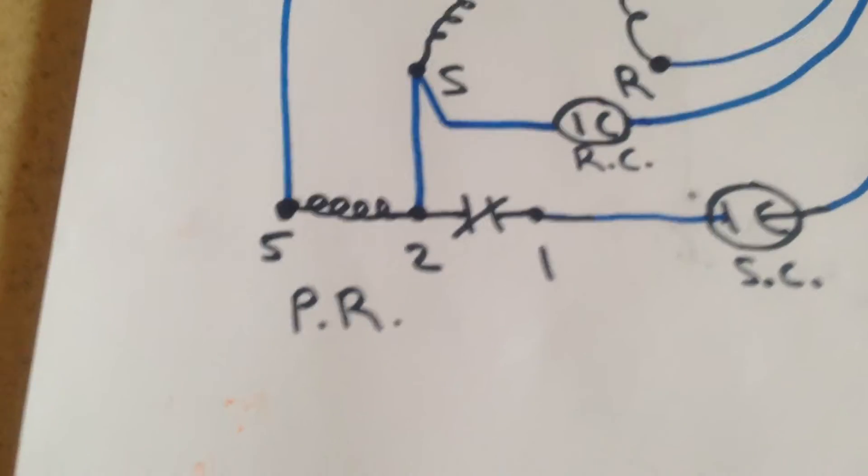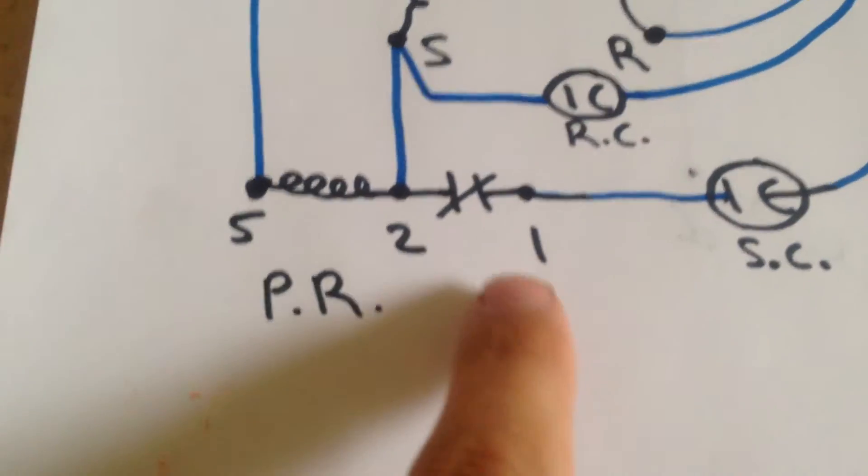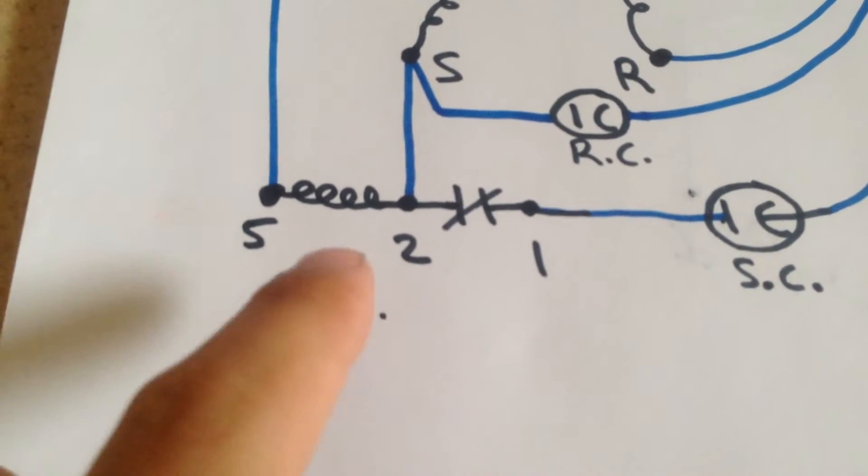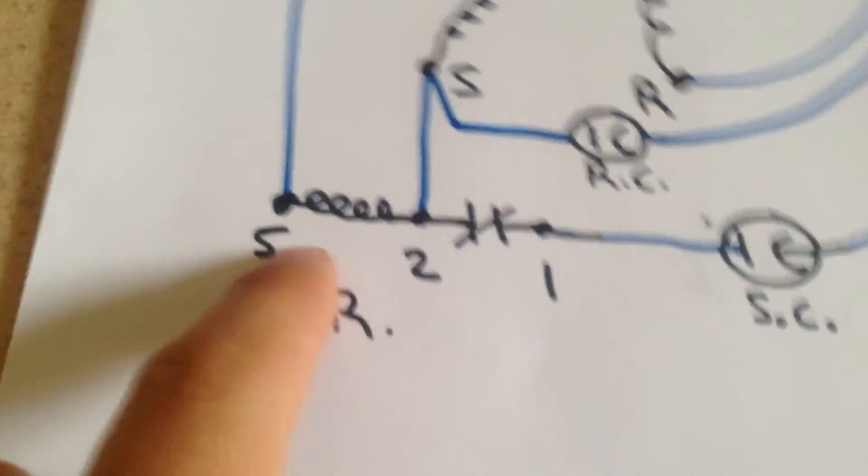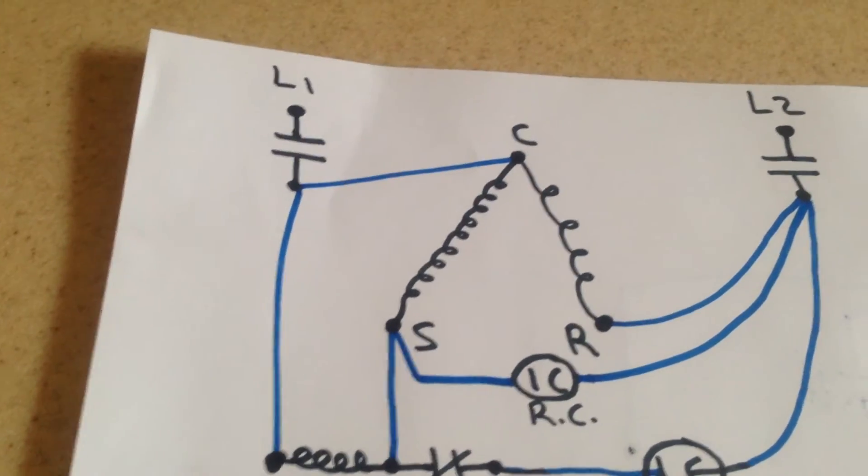So here's our potential relay in its de-energized state. It has a normally closed contact between 2 and 1, and our coil between 5 and 2. And the coil is going to get its voltage across the start winding.